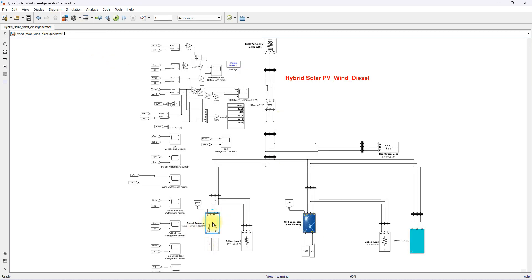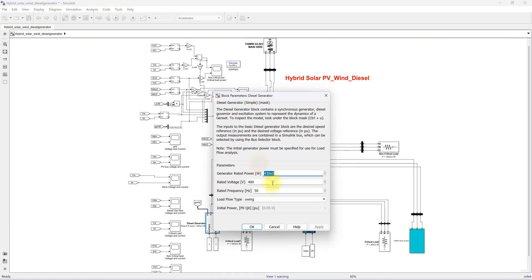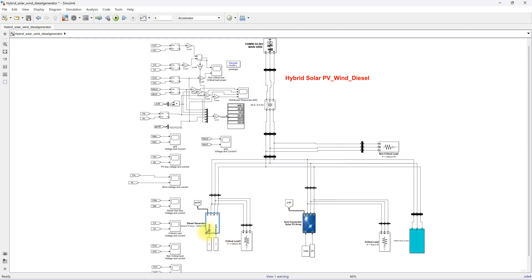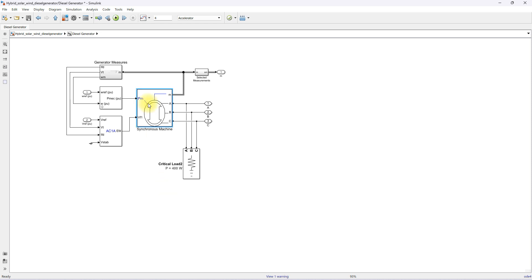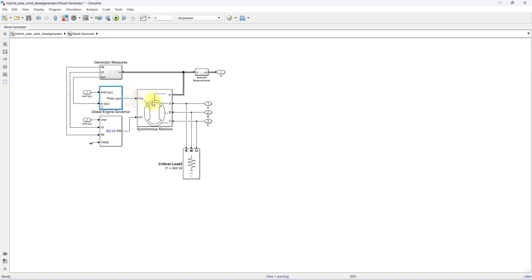Here you can see the diesel generator, rated at 430 kilowatts, with a rated voltage of 400 V and rated frequency of 50 Hz. Clicking inside, you can see it is a synchronous machine having a diesel engine governor and an excitation system. The diesel engine governor controls the mechanical input to the synchronous machine, and the excitation system controls the field of the synchronous machine to maintain terminal voltage at constant.